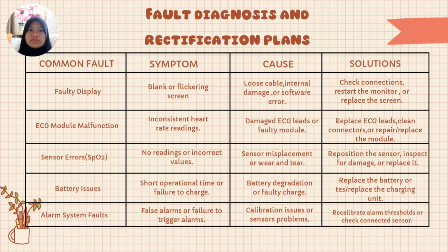After that, the common fault is sensor error SPO2. The symptom is no reading or incorrect value. It is caused by sensor misplacement or wear and tear. The solution is to reposition the sensor, inspect for damage, or replace it.